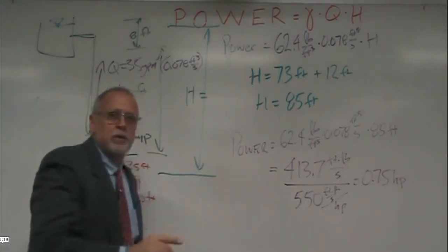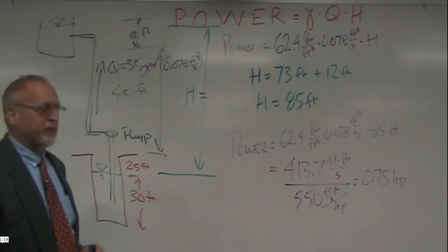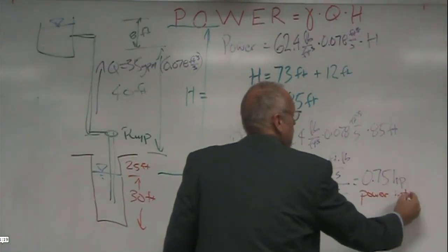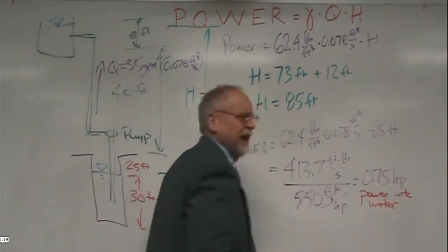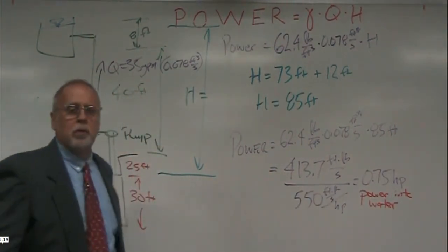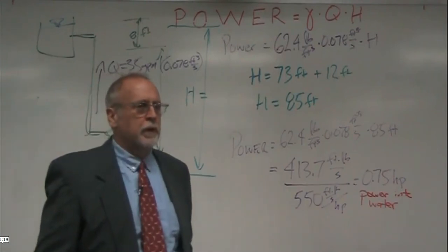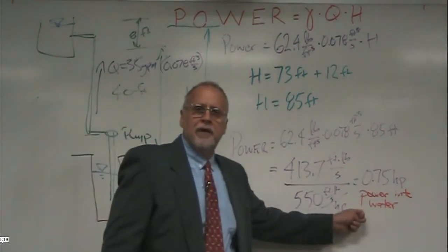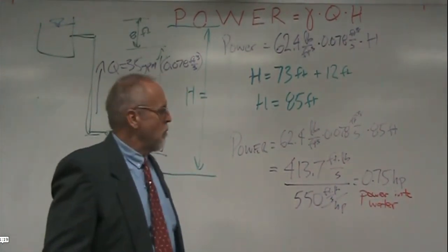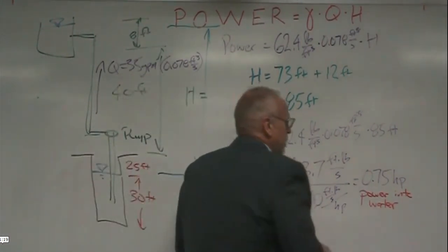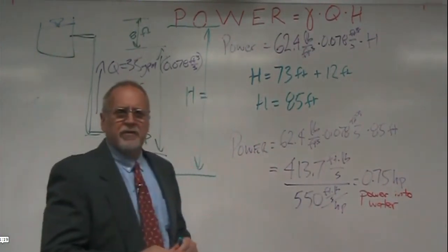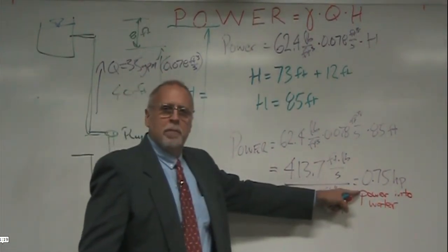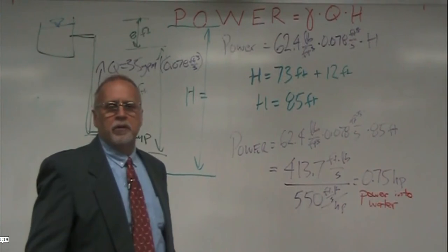But we are not finished yet. That is the power that's going into the water. What do you mean by that? Oh, it's a fallen world, my friend. Nothing is 100% efficient. The water needs 0.75 horsepower. That's the power it needs. But the pump is not 100% efficient. We have to send more power to the pump than that to get the power out into the water.